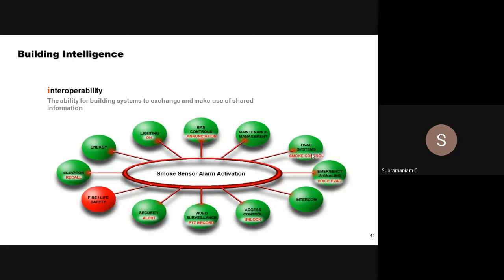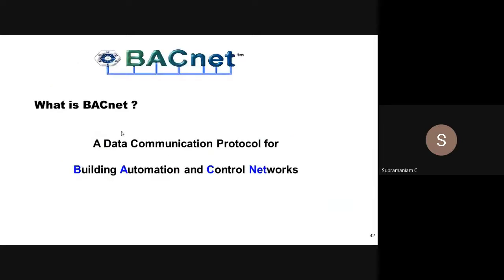The smoke control has to get activated because you want to stop all the AHUs. You don't want to spread the fire by keeping the AHUs on. Voice evacuation has to be called. The access control has to unlock. Video surveillance has to start recording, to see where the fire started, or whether there is any problem with people running to the ground level, and a security alert. So all this is communication. You want to share information from one system to other systems. How is it possible? That is possible only by interoperability, where you exchange information from one system to another. That is where BACnet becomes important.